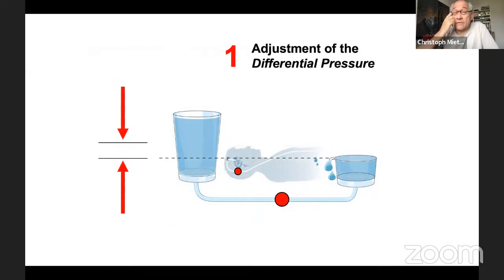So what does it mean, finally, to conclude? The adjustment of the differential pressure in the lying position, I think, has been overvalued. Very often, the adjustment has been used to address something which causes trouble in the upright position. If we have in this position a comparably low differential pressure, you will not see any over drainage if this is not the same or going to happen in the upright position.